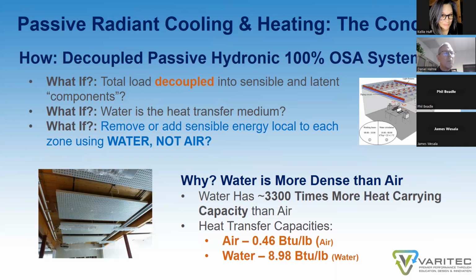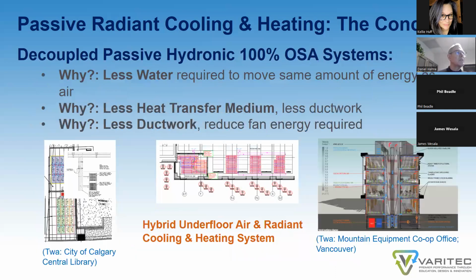Well, water, because it is a more dense heat transfer medium, has 3,300 times more heat carrying capacity than air. How is that? Well, air can hold, as I mentioned earlier, 0.46 BTUs per pound of air. Water can hold 8.98 BTUs per pound of water. Why? Because water is more dense than air. So why would we do that?